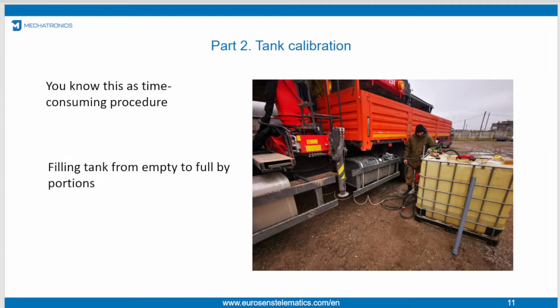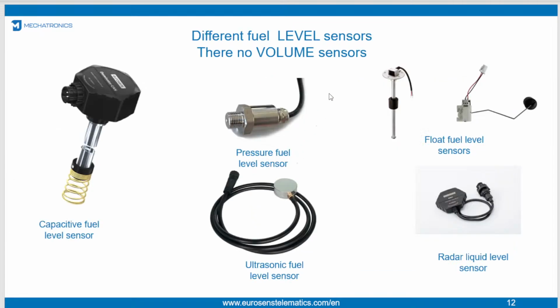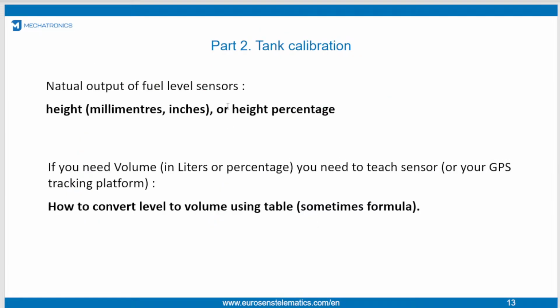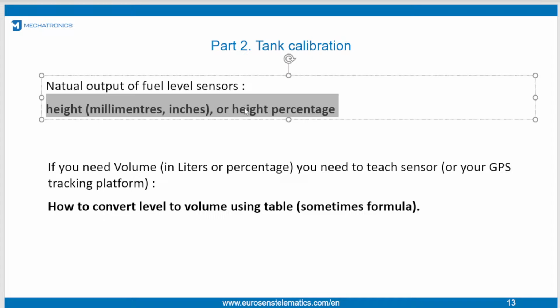And there are different types of liquid level sensors: capacitive sensors, pressure, ultrasonic level sensors. They are all level sensors, and the natural output is level. There are no fuel volume sensors on the market. So if you or your customer can be satisfied with height or height percentage, you don't need to calibrate the tank. You can use the sensor data already.